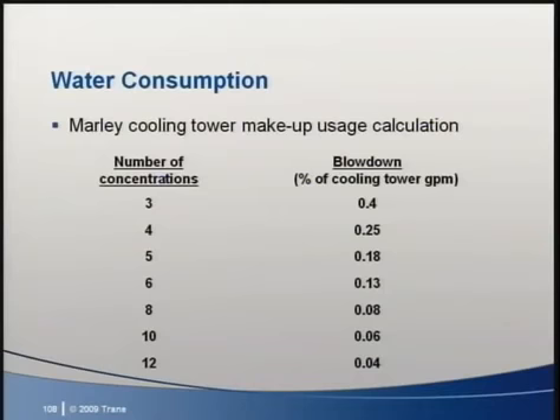The water of evaporation exits the tower in a pure vapor state, leaving behind its burden of total dissolved solids, TDS, to concentrate in the recirculating mass of water, jeopardizing not only the cooling tower, but the heat exchanger and all other water circuit-related components as well. The proper method for controlling TDS concentrations is called blowdown, where a portion of the circulating water flow is continuously wasted and replenished with relatively pure makeup water. In the 3.2 gallons per ton hour of heat rejection used by the program's standard heat rejection equipment, a concentration of about 2.5 was assumed. This is relatively clean water.